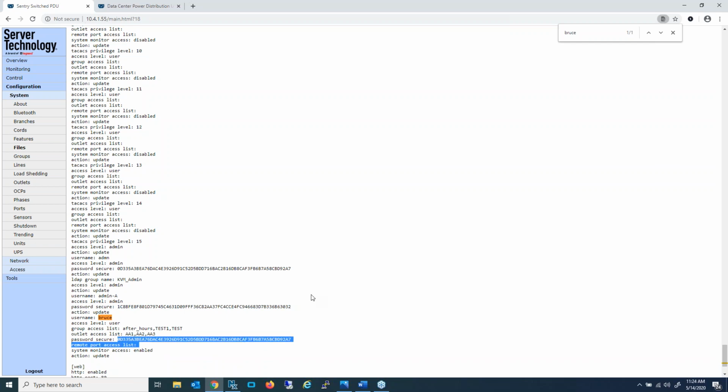So you'll have a master file that you'll be able to push out to all the different PDUs, and you'll just edit that file every 60 days, 90 days, whatever the policy is. The simplest method would be to use SFTP, Secure File Transfer Protocol, to push that INI file out to the various PDUs. So you don't need to log into each and every one; use SFTP to put the file to the PDU, and then it will be updated. And you'll do that across the board. You could most likely write a script to do that in a more automated fashion.